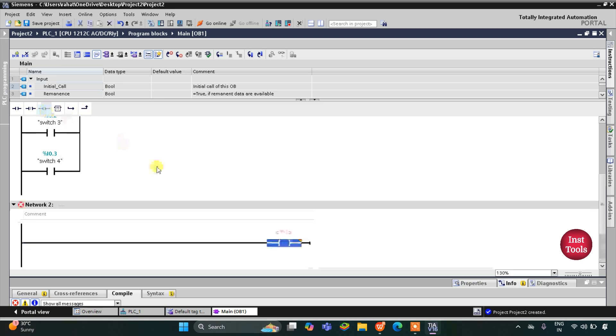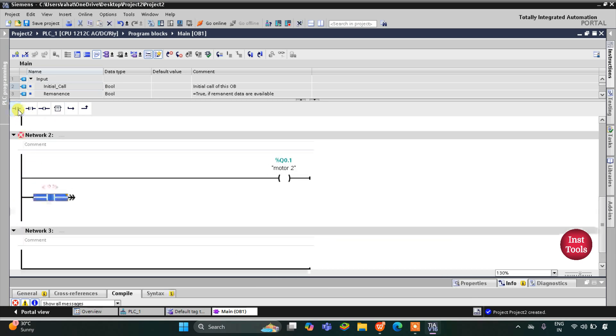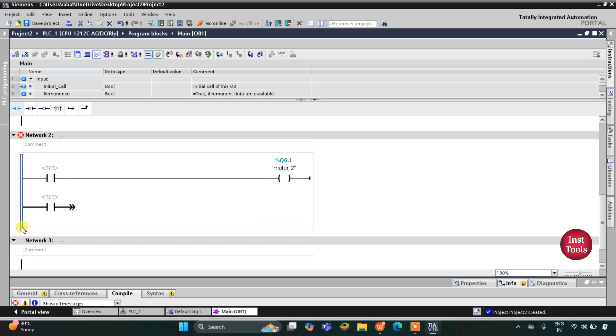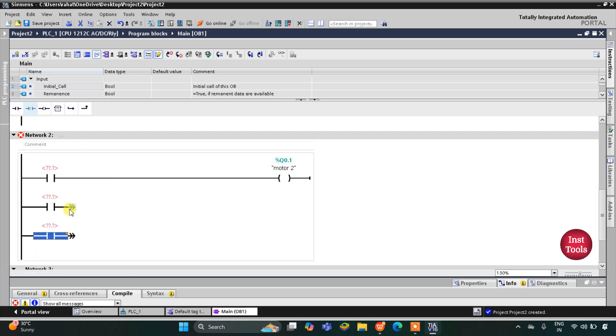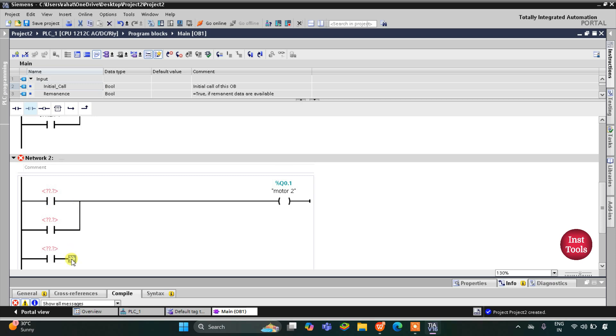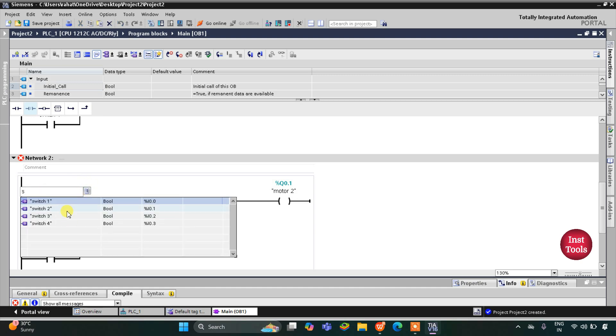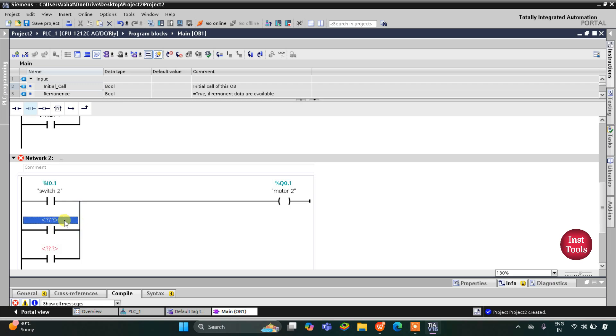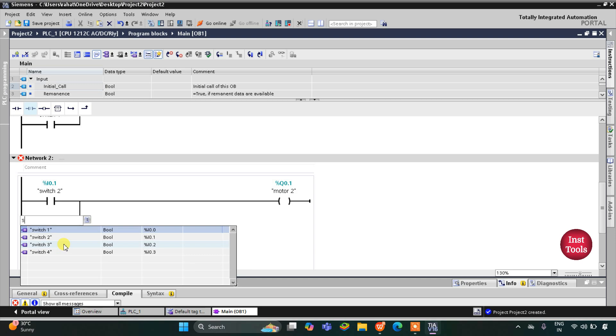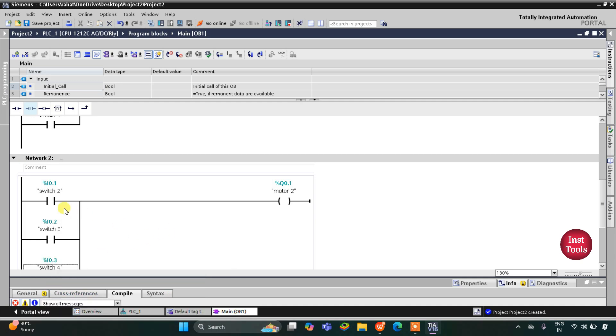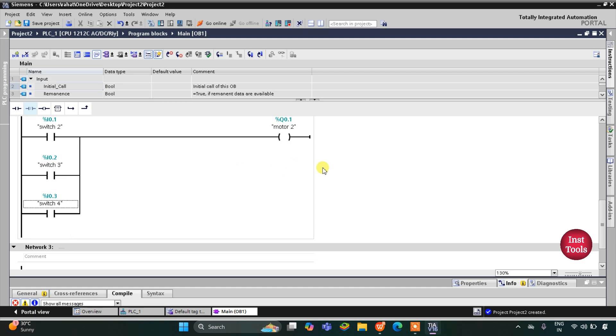Now I'll insert a coil for motor 2. I'll add normally open contacts and open branches using Shift+F9 to build the OR logic. The first contact will be switch 2, because switch 1 will not turn on motor 2 — it turns on only motor 1. Then switch 3, then switch 4. So if switch 2, switch 3, or switch 4 is turned on, motor 2 will be on.